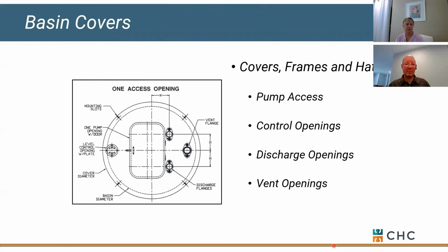Let's talk about pump covers real quick, or basin covers. A standard steel cover is good to about 300 pounds a square foot, so a heavy individual could walk across this, no problem. But if you're going to use a forklift or a pallet jack, or run a car across it, that could exceed the rating of that basin cover. So if it gets too heavy, depending on your load, we might need to have some special considerations for a cover.